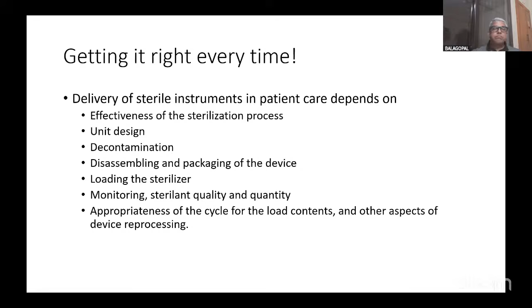To get it right every time, you need to know that the delivery of sterile instruments depends on the effectiveness of the sterilization process, the design of the unit, the decontamination, disassembling and packaging, loading the sterilizer, monitoring the sterilant quality and quantity, and appropriateness of the cycle. Cleaning has already been dealt with, so I'll go straight to the sterilization process.